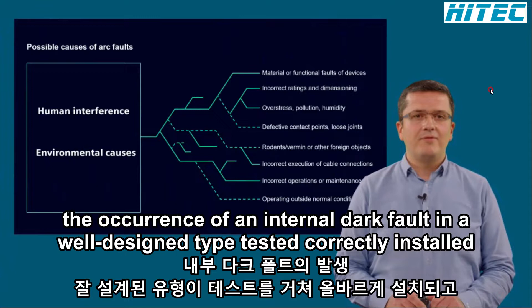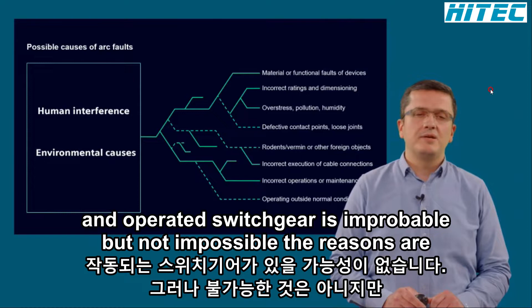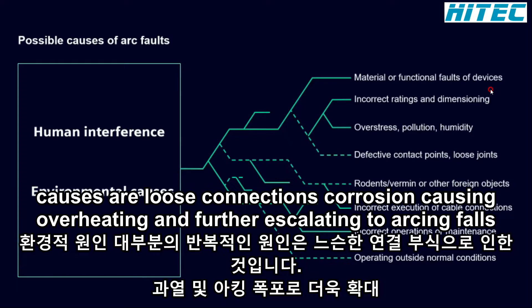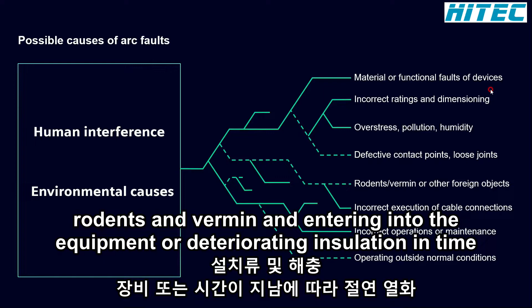The occurrence of an internal arc fault in a well-designed, type-tested, correctly installed, and operated switchgear is improbable, but not impossible. The reasons are mostly linked to human interference or environmental causes. Most repeating causes are loose connections, corrosion causing overheating and further escalating to arcing faults, rodents and vermin entering into the equipment, or deteriorating insulation over time.